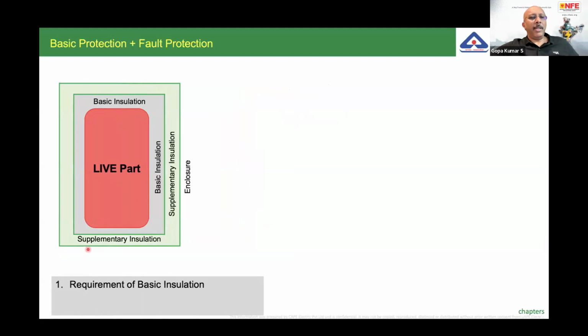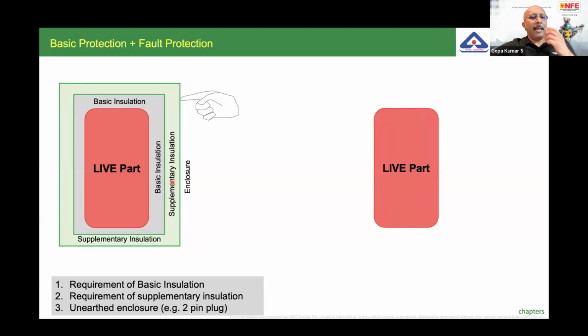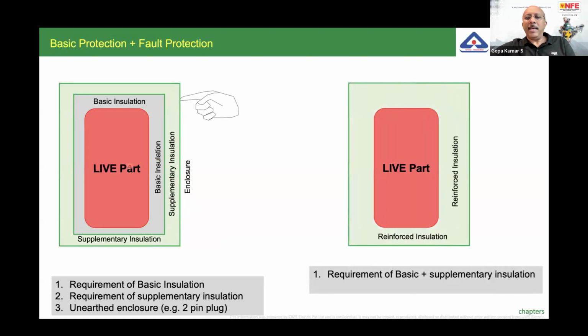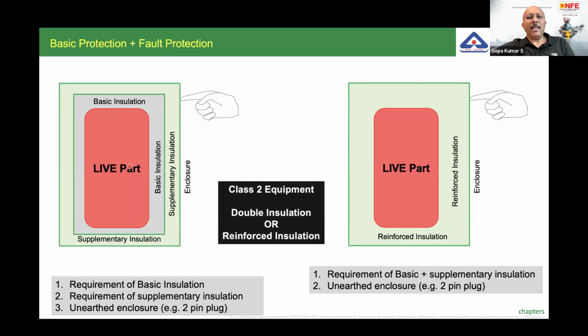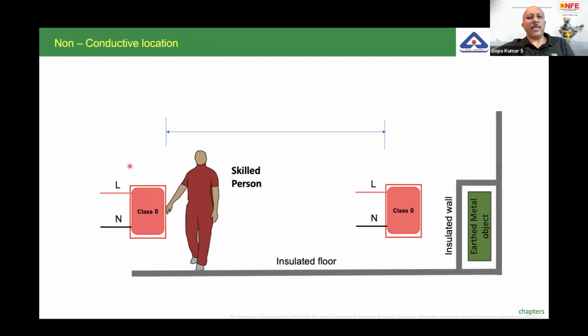Similarly, double insulation. Double insulation means the live part has a basic insulation, and you have an additional, a supplementary insulation as well. As a result of this double insulation, even if there is a fault, the person handling this particular equipment does not get a shock. Example, equipment with a 2-pin plug. Similarly, the basic and supplementary insulation can be replaced with reinforced insulation, that means very strong insulation. The internal fault is not creating a shock situation. In both these cases, equipotential bonding or earthing is not necessary, and these equipment are called class 2 equipment, double or reinforced insulation.